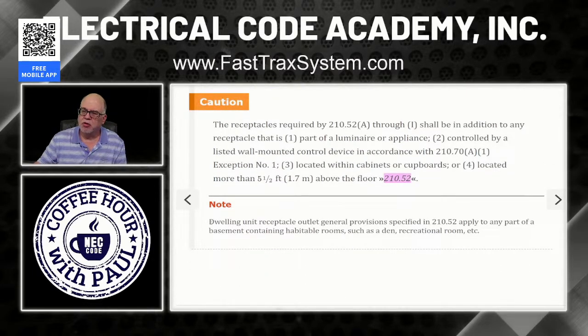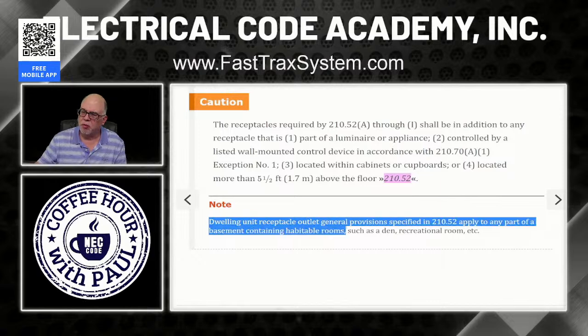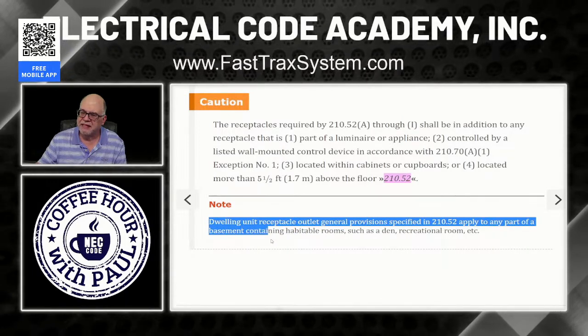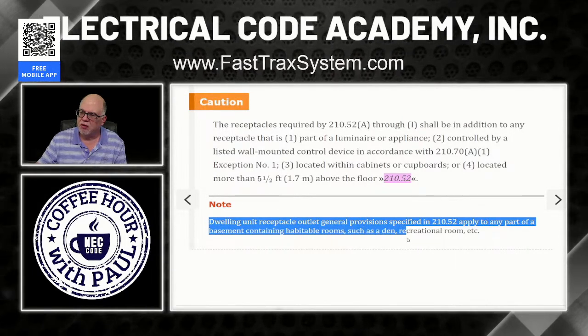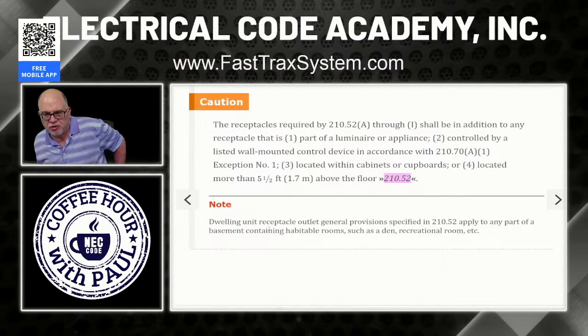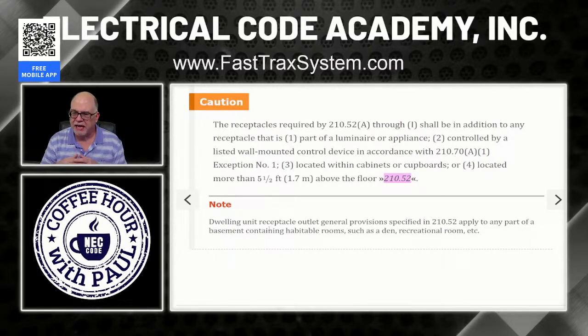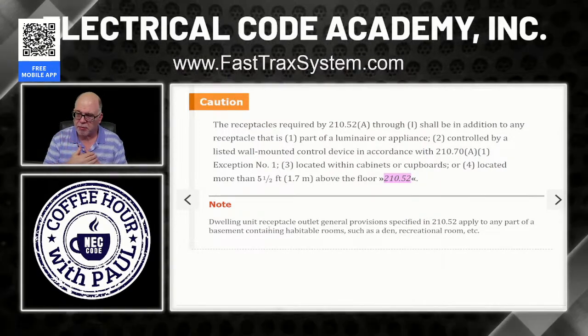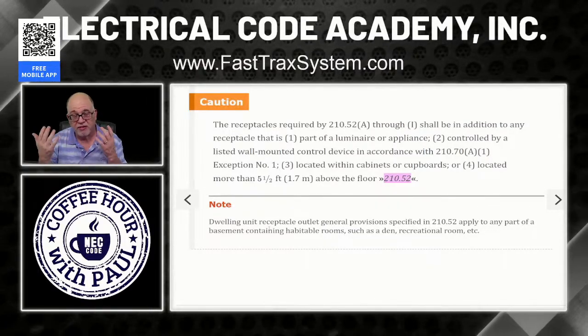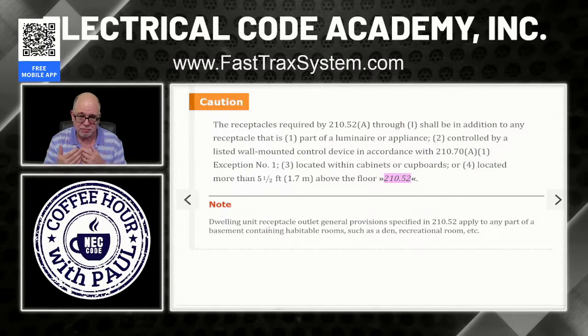All right, note: dwelling unit receptacle outlet general provisions specified in 210.52 apply to any part of a basement containing habitable rooms such as dens, recreation rooms, etc. So again, downstairs, if you have dwelling unit receptacles and you have a basement, then guess what? If it's considered a habitable room, and it will be, you have to make sure that you still meet the spacing requirements down there as well. Now, if it's an unfinished basement, no, you don't. Okay. But if it's a finished basement, this 210.52 is going to apply to spacing of the receptacles.